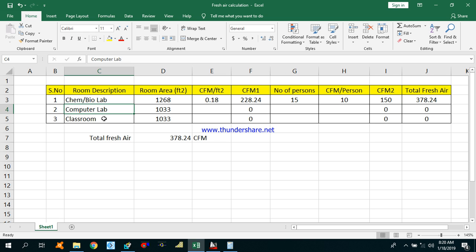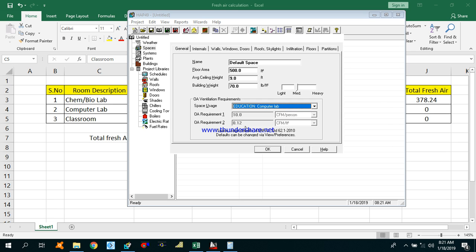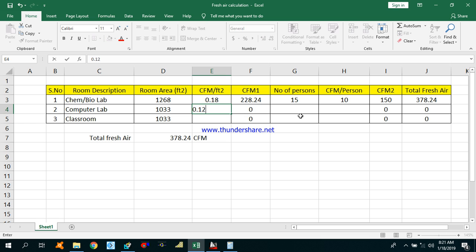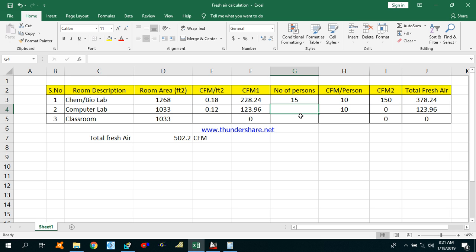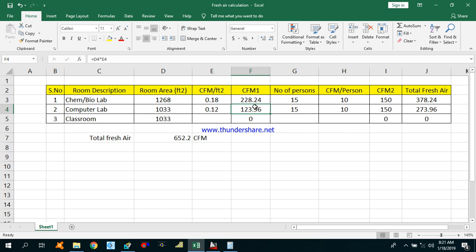In the same way you can calculate CFM for the computer lab. In the HAP software under Education, select Computer Lab. The CFM per person is 10 and the outdoor air requirement is 0.12 CFM per square feet. Using the same number of persons, room area multiplied by CFM per square feet gives CFM1, and number of persons multiplied by CFM per person gives CFM2. Total CFM for the computer lab is approximately 274 CFM.